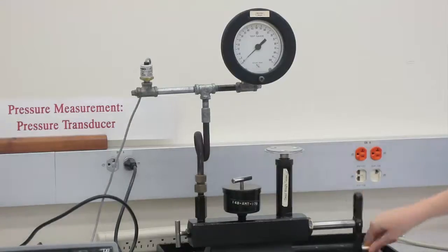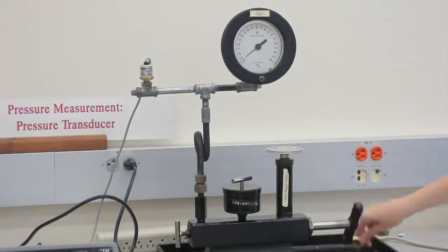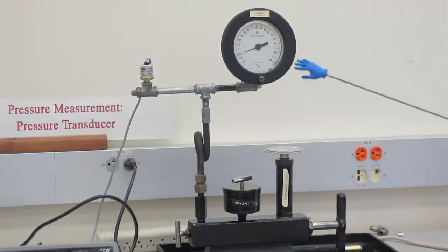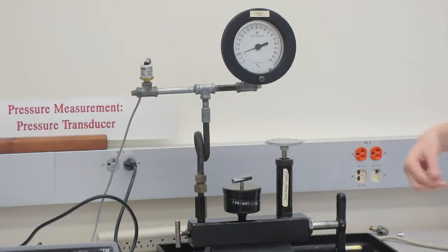Now we're ready to prepare the dead weight tester. With no weight added, crank the hand wheel so the Bourdon gauge reads about 10 psi. Give the weight platform a gentle push and a short spin.